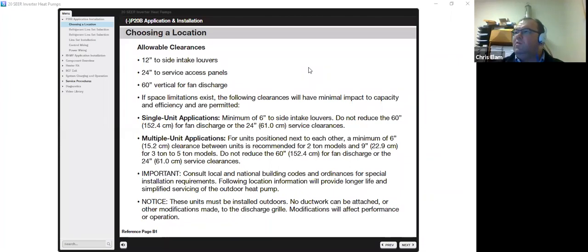Okay, we'll start off here with choosing a location. It is important to allow 12 inches to the side intake louvers, 24 inches to the access panels, and 60 inches vertical for the fan discharge. If space limitations exist, the following clearances will have minimal impact to capacity and are permitted. If you have single unit applications, minimum of 6 inches to louvers. Do not reduce the 60 inches on the fan discharge or the 24 inches for service clearance.